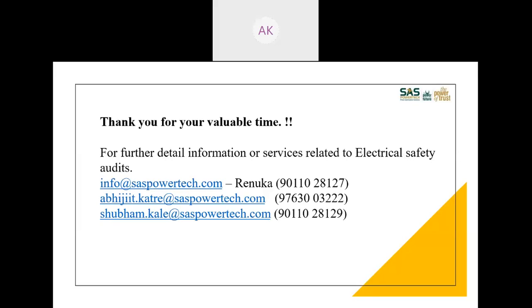Yes, for any transformer fence, you should do earthing. What is the harm? You can connect it to the earth grid created in and around your plant. The main problem is, suppose you have an open type of transformer substation where, from your two pole structure, the cables come directly to the transformer primary bushing. If there is a breakage in those cables, or in the incoming line terminated on the two pole structure, and it falls on your fence, then it is better if you have earthed it properly.